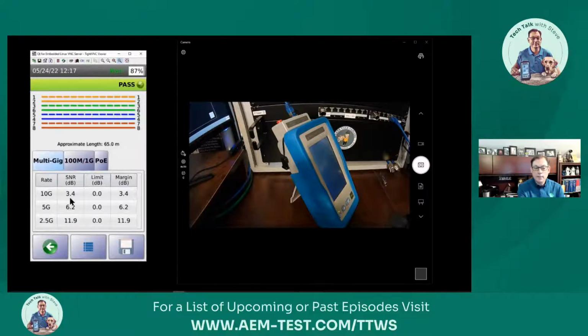3.4 is okay - I've got 10 gig here at 3.4. Really, it's going to be based on the typical good working link in your specific network as to what this should be. The rule of thumb for 10 gig is I wouldn't want to see anything less than 3 dB, but I'd test some known good working cables. If all of those were exhibiting 4 or 5 dB, that's my benchmark, and maybe I'll set my limit higher. Then if I have one that fails, I can take a closer look at it.